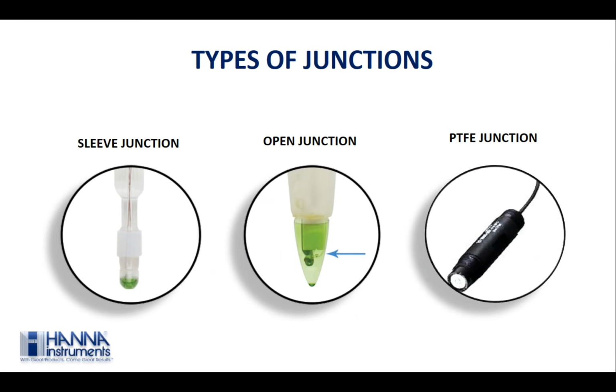This is said to be a CPS technology. CPS means clogging prevention system technology. This utilizes the porousness of ground glass coupled with a PTFE sleeve to prevent clogging of the junction. The ground glass allows proper flow of liquid while the PTFE sleeve repels the solid. As a result, pH electrodes with CPS technology take up to 20 times longer to be fouled as compared to conventional electrodes.